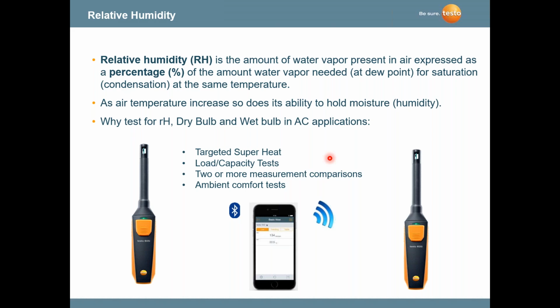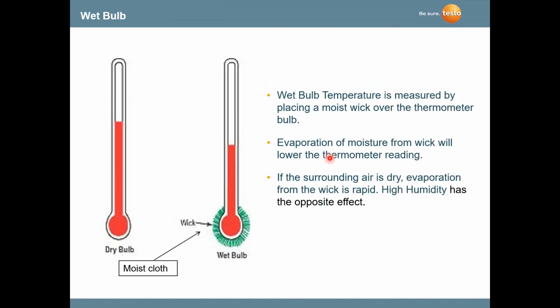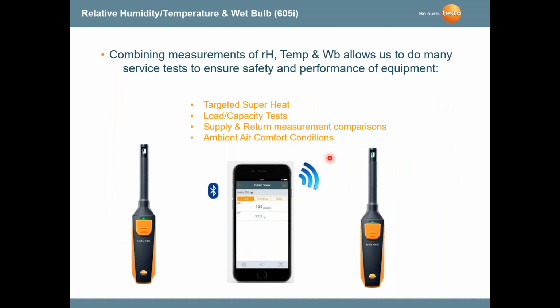Instruments today are primarily digital. When they're digital, they can measure relative humidity and the dry bulb or ambient temperature, and we can calculate the wet bulb from those measurements. Basically, wet bulb relates to the amount of moisture in the air versus the ambient. We used to use a sling psychrometer with a dry bulb and a wet bulb. As we spun the sling psychrometer, airflow went over the wet bulb, which was moist with water, and we could determine the evaporation point of water and how it affects the temperature. That was considered the wet bulb reading, and from the wet bulb and dry bulb readings, we could get the relative humidity.